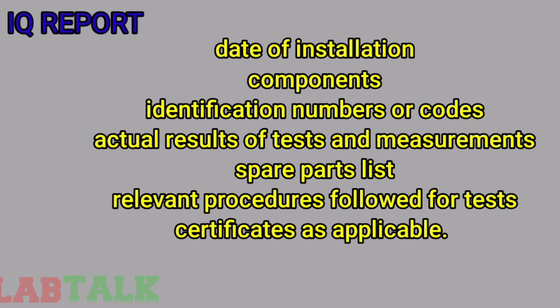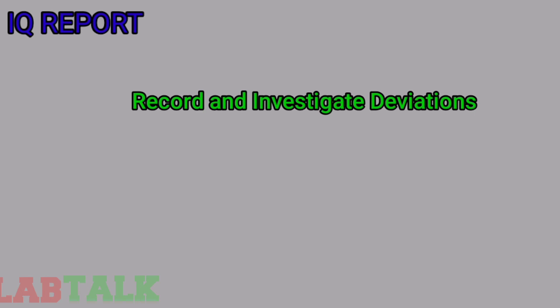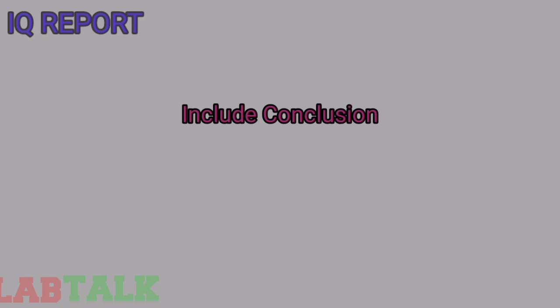actual results of the tests and measurements that are performed during installation qualification, list of spare parts, relevant procedures followed for tests, and certificates as applicable. All the deviations and non-conformances from the URS, that is user requirement specification or design qualification, and acceptance criteria specified, observed during installation, should be recorded and investigated. The outcome of the IQ should be recorded in the conclusion of the report before OQ, or operational qualification, is started.